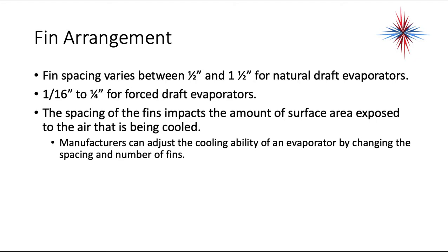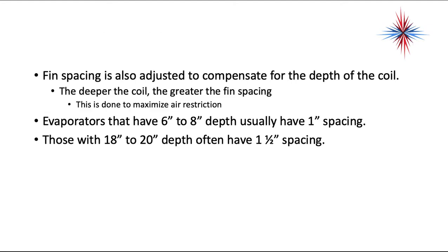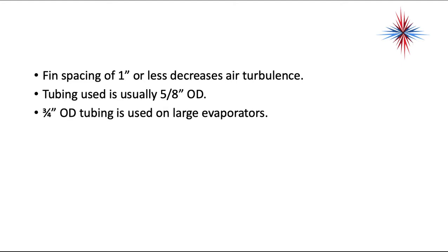Fin spacing varies between half-inch and one-and-a-half-inch for natural draft evaporators, and one-sixteenth-inch to one-quarter-inch for forced draft evaporators. The spacing of the fins impacts the amount of surface area exposed to the air being cooled. Manufacturers can adjust the cooling ability of an evaporator by changing the spacing and number of fins — the more fins, the more surface area exposed to the air stream. Fin spacing is also adjusted to compensate for the depth of the coil; the deeper the coil, the greater the fin spacing, to maximize air restriction. A fin spacing of an inch or less decreases air turbulence.